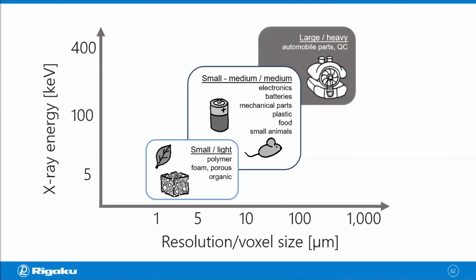The third category is for small and light materials, like polymers, foams, organic materials, including plants and insects. And for that area, you need a low energy X-ray source, anywhere from 5 keV to 15 or 20 keV. And because the structures you're trying to image here are often very small or fine, you need a little bit higher resolution, going down to 1 micron or sometimes even a couple hundred nanometers. So that's the third category. And again, those are three major groups or categories of X-ray CT scanners. And one of the major differences between the three is the X-ray energy their sources have.